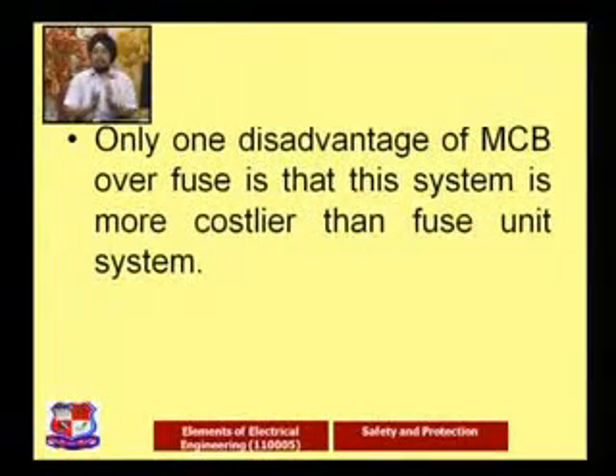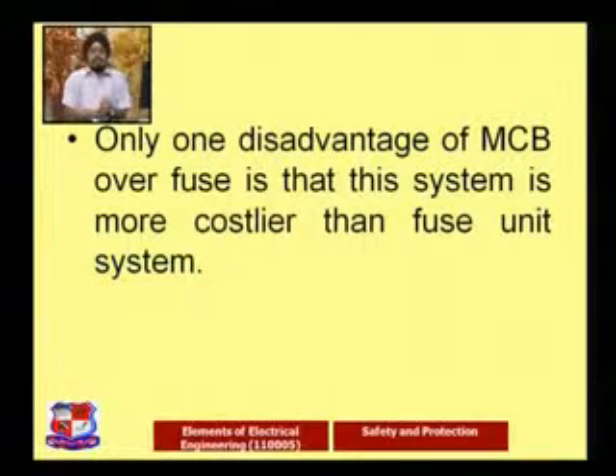The one big disadvantage of the MCB over the fuse is that it is obviously costlier compared to the fuse. For operating and understanding it we require some knowledgeable person, but a fuse can be wired by any person. Obviously, if the gauge, as we discussed, is higher, the fuse is never going to burn out, but it may happen that the circuitry burns out. So the MCB is costly, but at the same time its precision, handling capacity and sensing capacity are much better than the fuse.